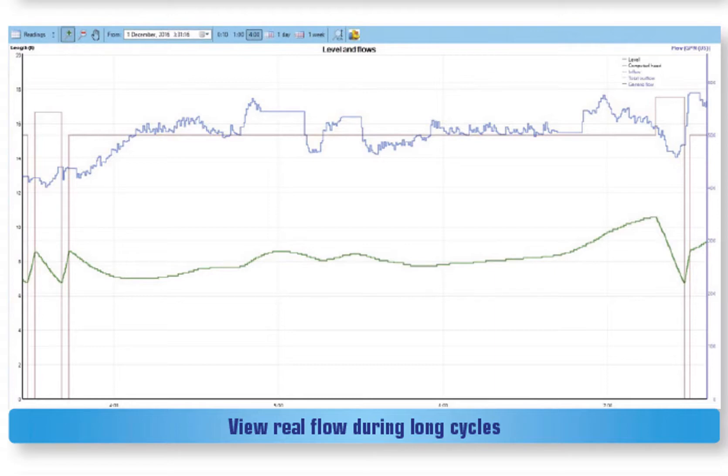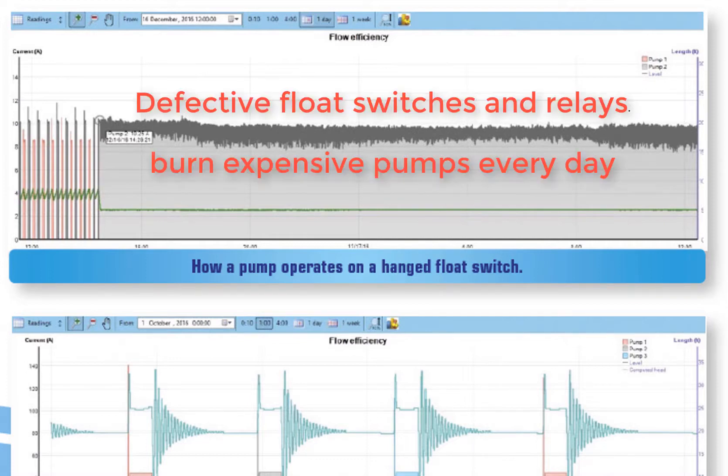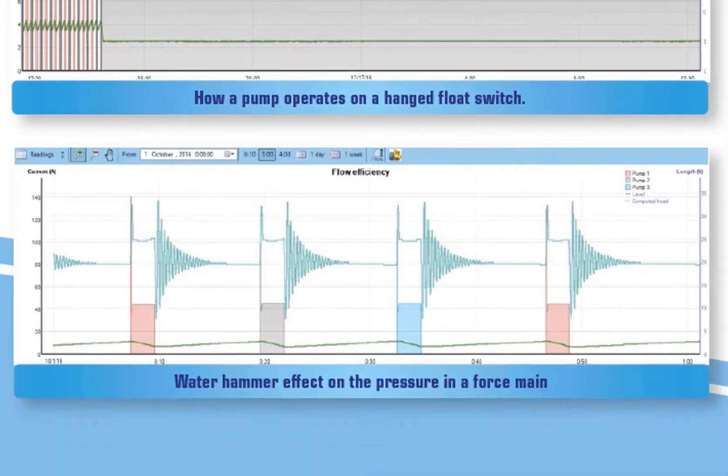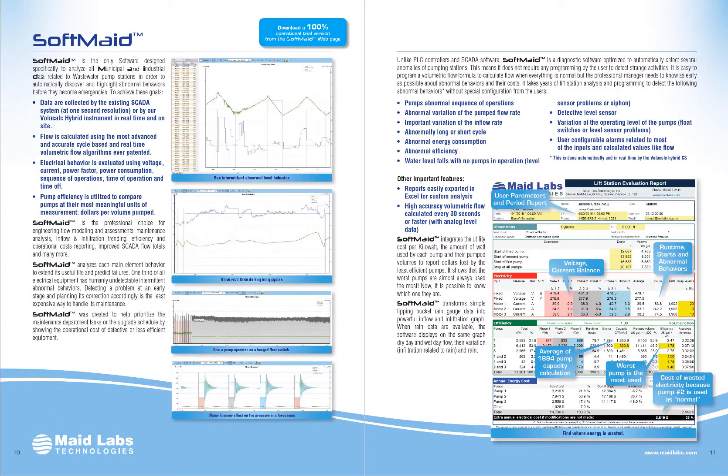When pacing a sampler proportional to flow rate during a very long cycle, the sampler will take samples at the wrong rate if you're waiting until the end of that cycle to calculate the pulse rate. In the other graph, we see what happens when a float or relay became defective. In this case, the relay that starts the pump and was supposed to stay on until the pump stopped was defective — so the pump was starting, stopping, starting, stopping until the pump burned. On the last graph you can see the water hammer effect on the force main. It can take up to three minutes for the pressure to get back to normal. There's a lot of analysis that can be done with SoftMaid just with the graphic mode.